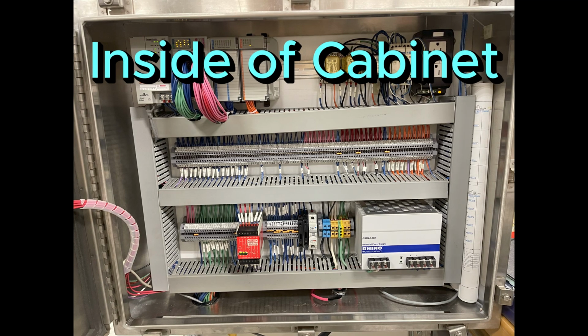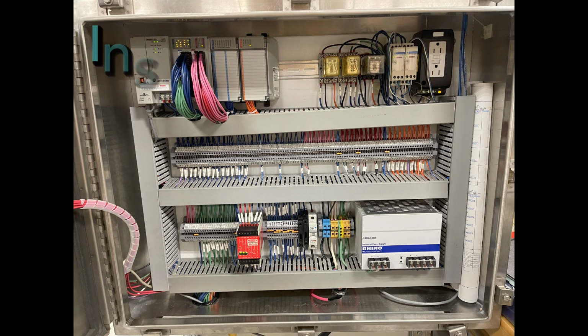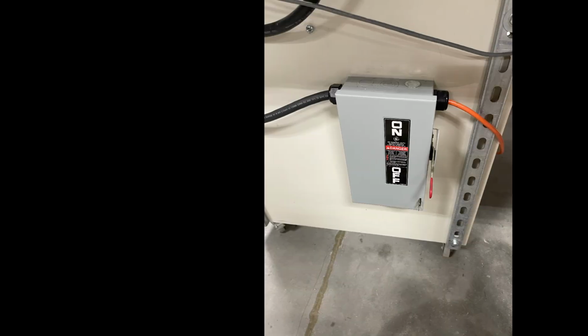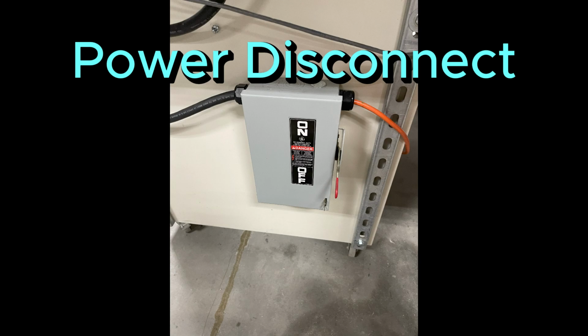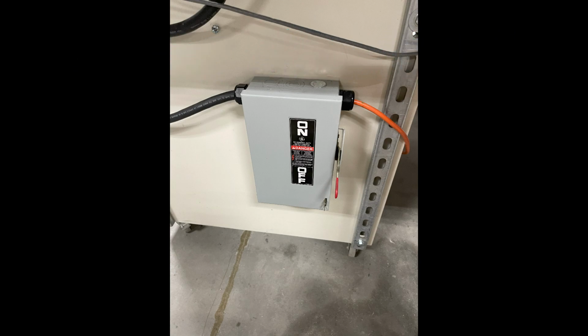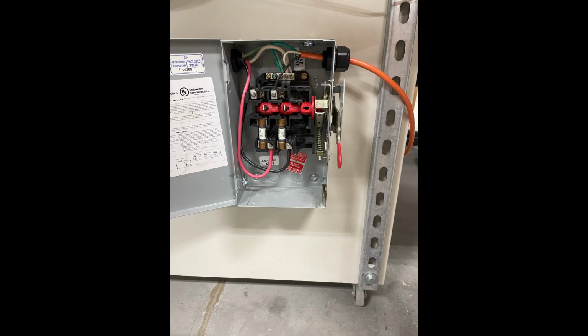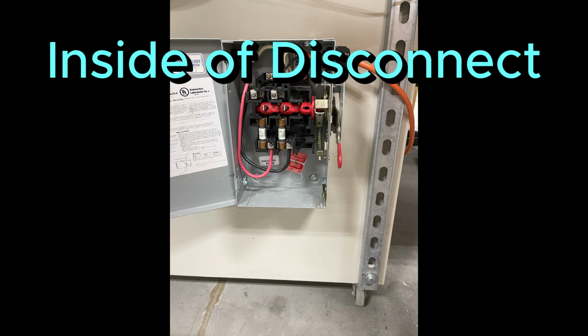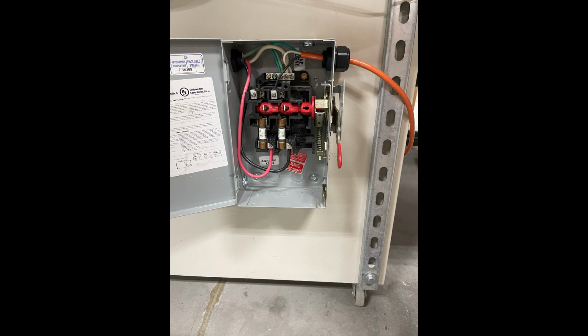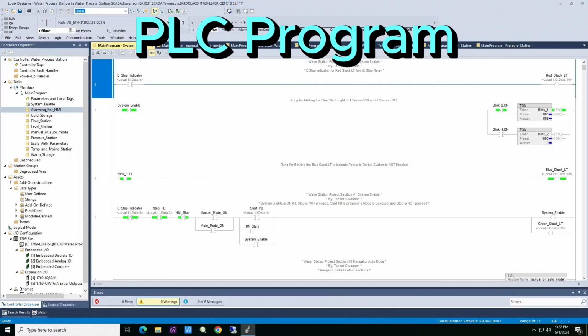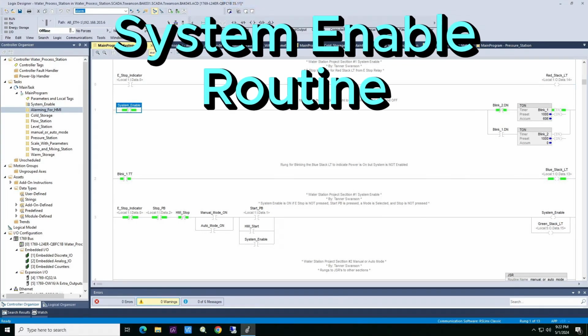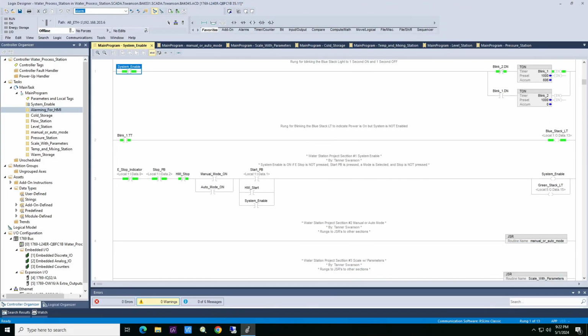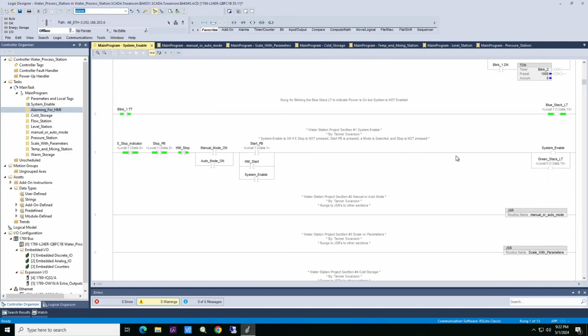Here is the inside of the cabinet. The PLC and then the power supply and e-stop relay, all my inputs and outputs. Here's my disconnect that I added underneath the cabinet. And then there's the inside wiring to it. And then going over the PLC program, first starting off with the system enable, where you will turn on the station. And then underneath you have all the JSRs to jump to the rest of the subroutines.